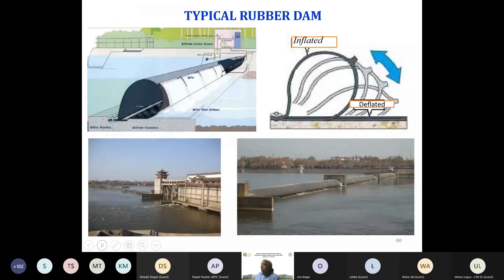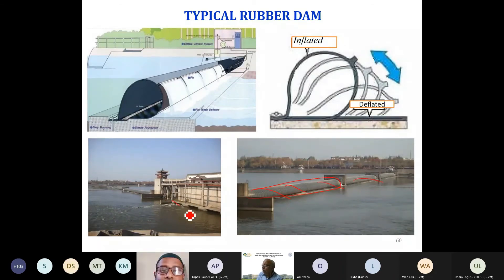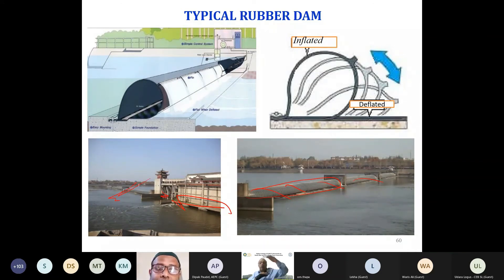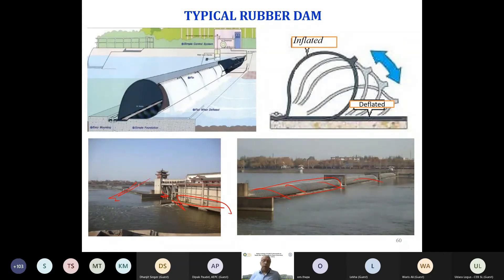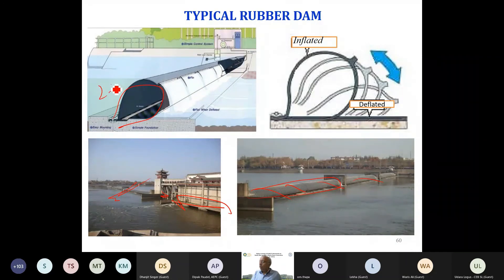A rubber dam layout: install a rubber dam to create a small two or three meter head, with the powerhouse alongside and a spillway for excess flow. Such possibilities exist on small streams throughout the SAARC region — in Sri Lanka and other countries. This option is heavily promoted because you can create just two meters of head and still generate meaningful power, even from very small streams.